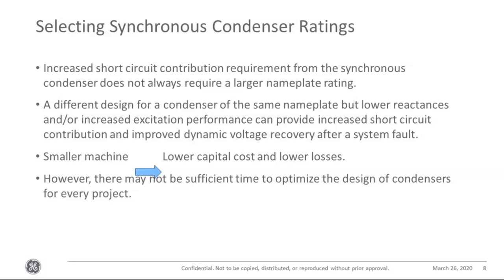You can get away using a smaller machine if you're focused on the short circuit requirement, and you don't need that higher output sustained for a longer term, because over a longer term, you can't exceed the nameplate rating. For a shorter term, you don't need that large nameplate rating. So it means you can have lower cost and lower losses. That said, sometimes by the time it is realized in a project that a synchronous condenser is required, there may not be sufficient time to optimize the design of the condensers, and you may have to go with something off the shelf.